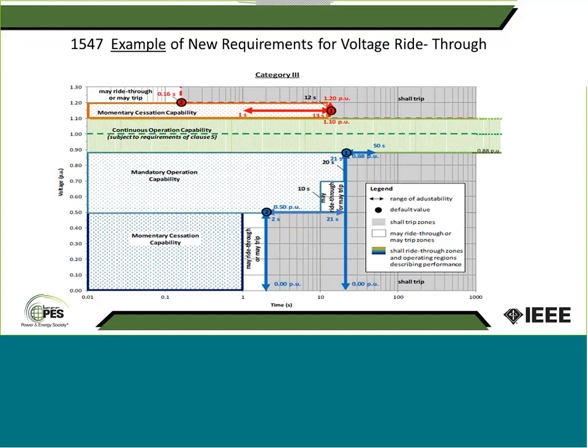I just put an example of what you're going to see in the standard when it comes to voltage ride-through. This is just a category 3 voltage ride-through figure. Of course, you're going to see one for category 2 and one for category 1, but the whole concept is the same. We want the generating DERs to stay on and support the grid during bulk system disturbances. And so let's go through this figure for a second, just to make sure we can all understand how to read it.